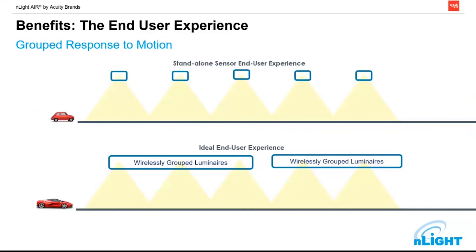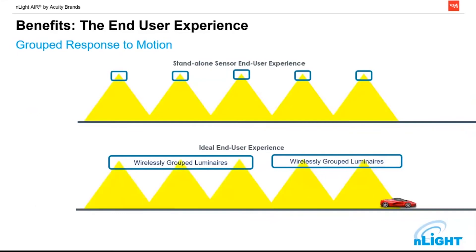Take the example of driving down an aisle. When motion is detected, we go up to 100%. If we want to be really aggressive with energy savings — because forklifts are coming in and out infrequently — after two minutes of nobody being in there, all fixtures in the aisle dim back down to 20 or 30%. We have a little glow for safety reasons but lights aren't at full brightness. Typically fluorescent fixtures came standard with a 15 or 20-minute timeout, so fixtures were going off incrementally and it was 15 to 20 minutes before that happened.